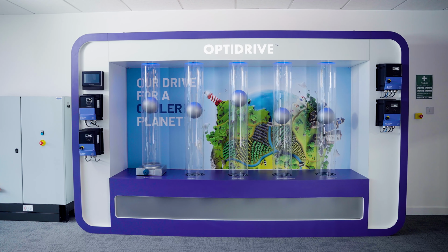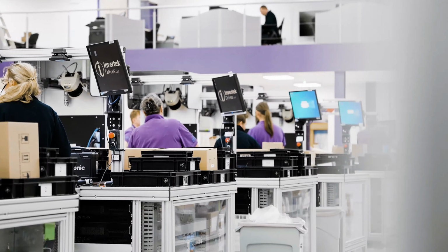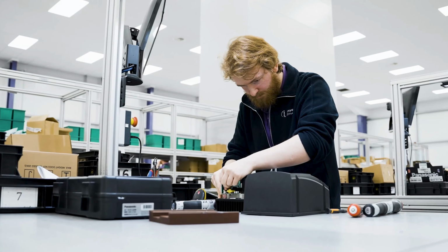One of the key reasons why we chose to integrate this room is of course the usage of variable speed drives on fans. It is one of the biggest sectors. It's a relatively simple application, but there can be many very subtle technical details that need to be considered. For example, in building ventilation it might be necessary to have a fire mode for smoke extraction or keeping fresh air into areas where occupants need to be evacuated safely.